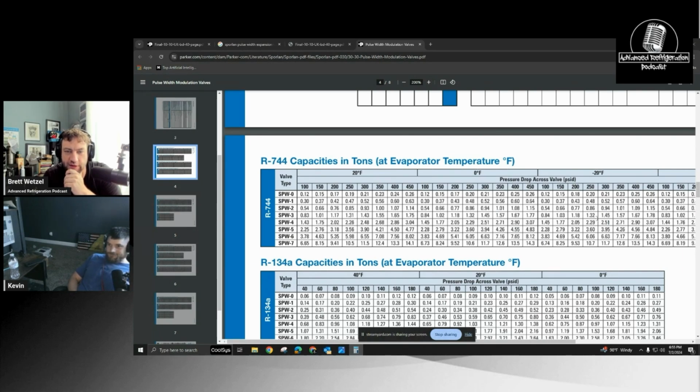So now you have a much higher pressure drop across the expansion valve. The flood back from the expansion valve was so violent that before the Core-Link could even react to look at the PID, in 6 seconds, it was shoving so much liquid down the suction line that the entire rack was shaking.